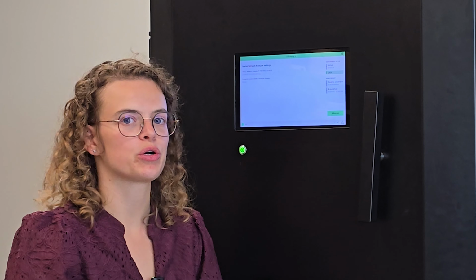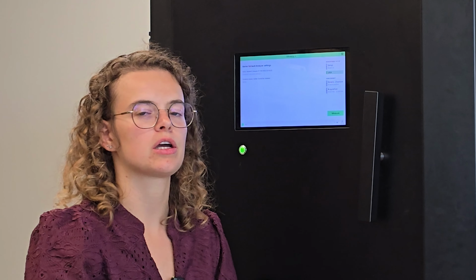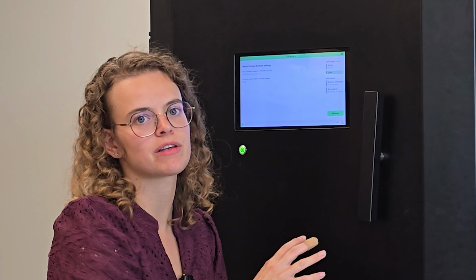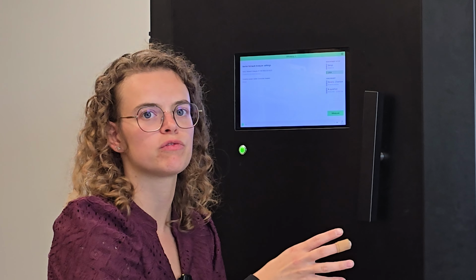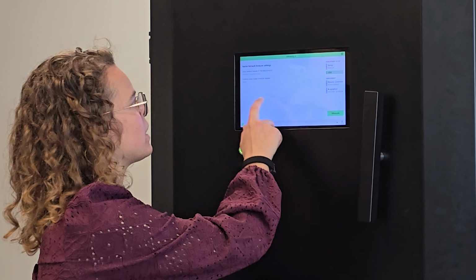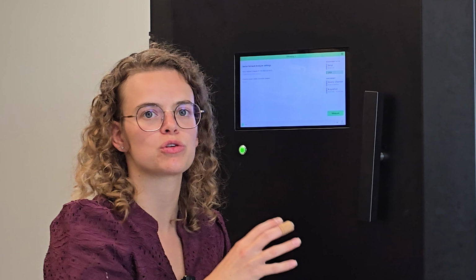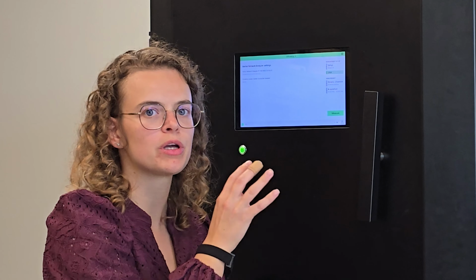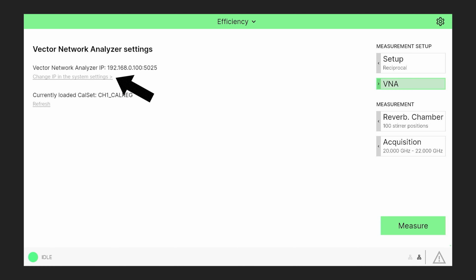You need to make sure that your VNA is, of course, connected to the chamber itself. For this, we have a simple Ethernet cable going from the chamber to the VNA. Actually, in this case, my laptop, because my laptop is controlling the VNA. And for that, we set the IP address of the Ethernet connection of my laptop inside this chamber, which you can do in the system settings.